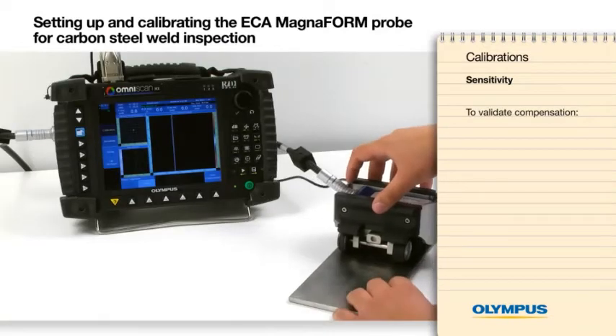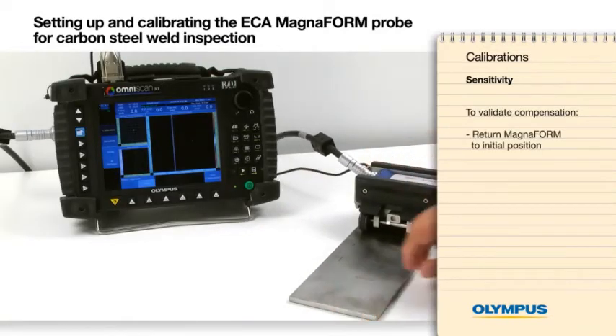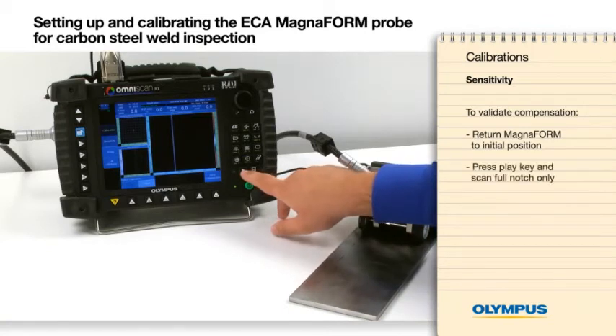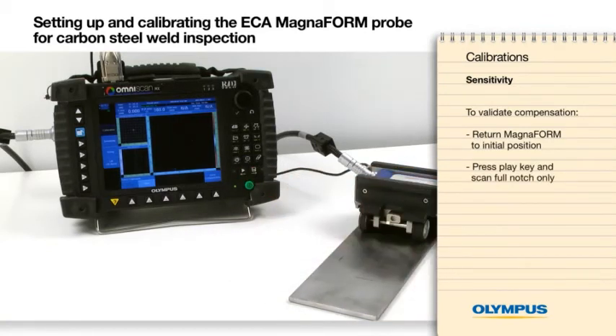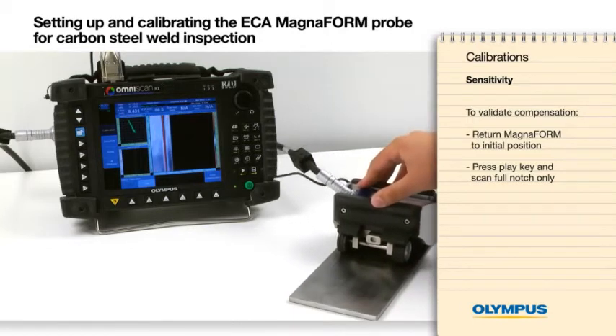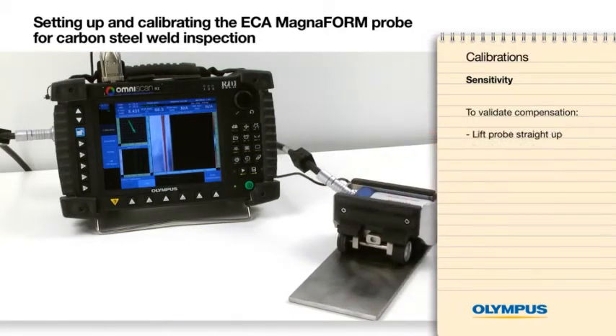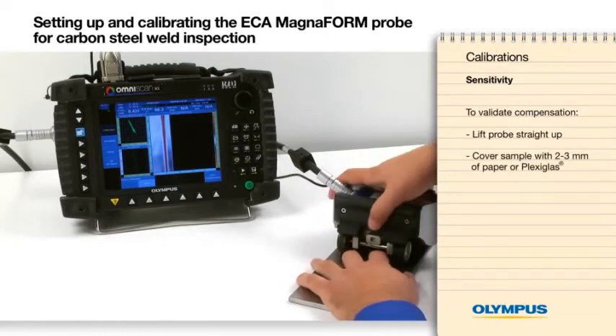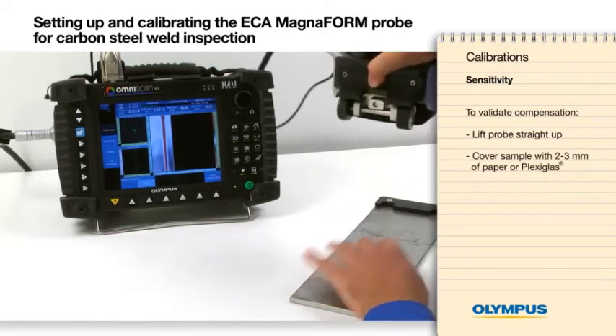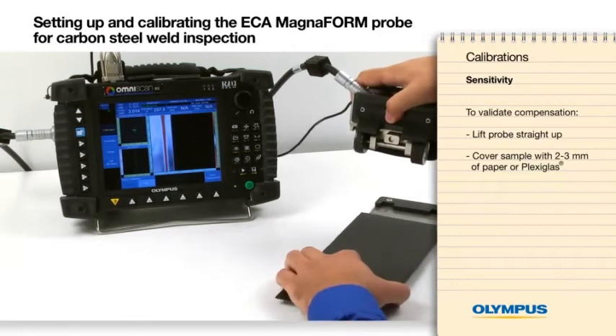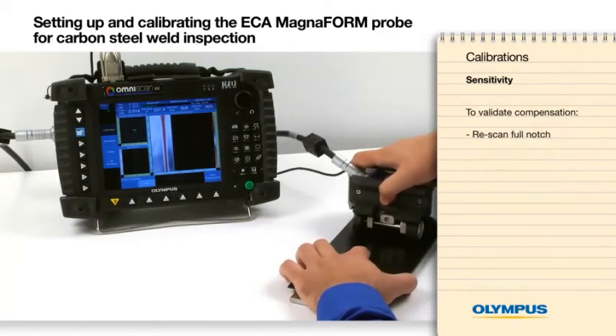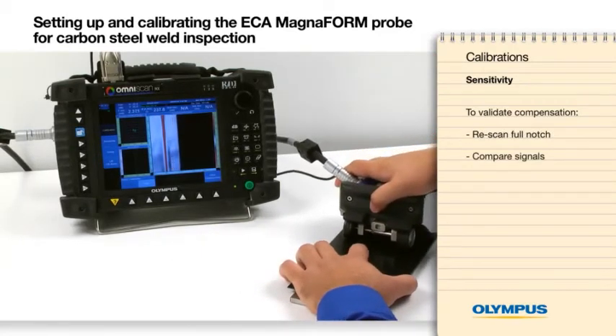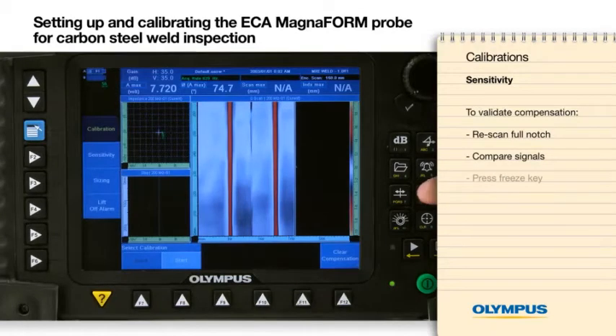To validate the compensation, return the probe to the starting position on the sample. Press the play key and then scan the full notch only. Lift the probe straight up and then cover the sample using 2 to 3 millimeters of paper or plexiglass. Rescan the full notch and compare the signal on screen. Press the freeze key.